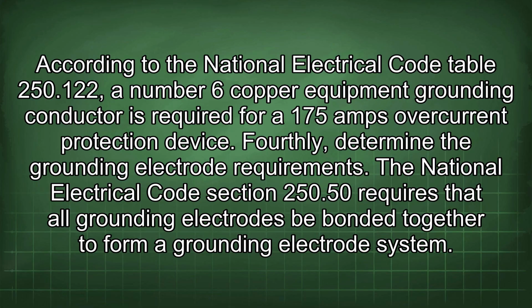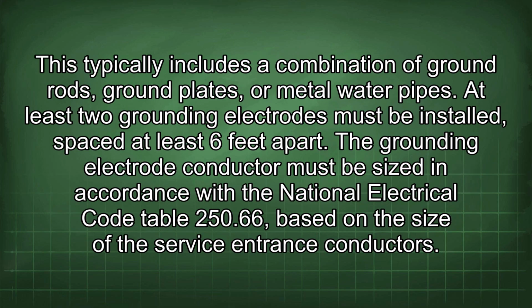The National Electrical Code Section 250.50 requires that all grounding electrodes be bonded together to form a grounding electrode system. This typically includes a combination of ground rods, ground plates, or metal water pipes. At least 2 grounding electrodes must be installed, spaced at least 6 feet apart. The grounding electrode conductor must be sized in accordance with the National Electrical Code Table 250.66, based on the size of the service entrance conductors.